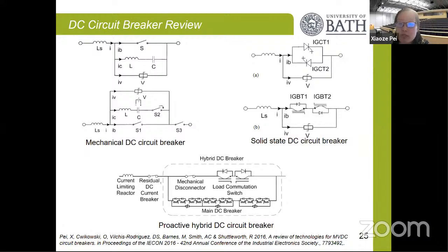So the second option is a power device, a solid state DC circuit breaker using semiconductor devices. We know that, for example, the IGBT and the IGCT control devices are able to interrupt the fault quite quickly. However, they have high on-state losses, which means they impact the system efficiency. That is why ABB came up with a hybrid structure.